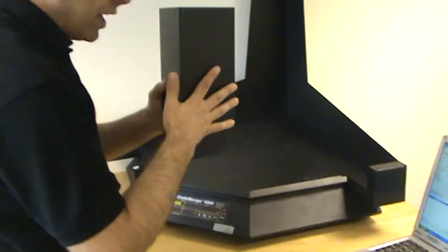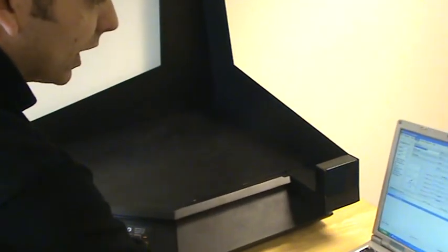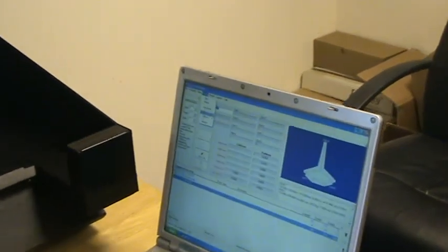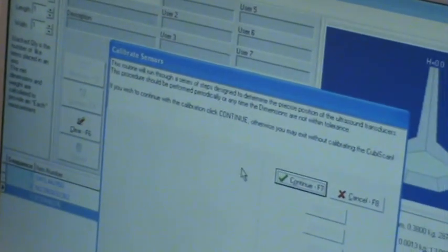This block here is our calibration block, and again using the software, we just go down to calibrate. In this instance we're just going to do the sensors. Do you want to continue? We do. It's just saying here it's going to take us through a routine that's going to help us calibrate it. Do you want to continue? We do.